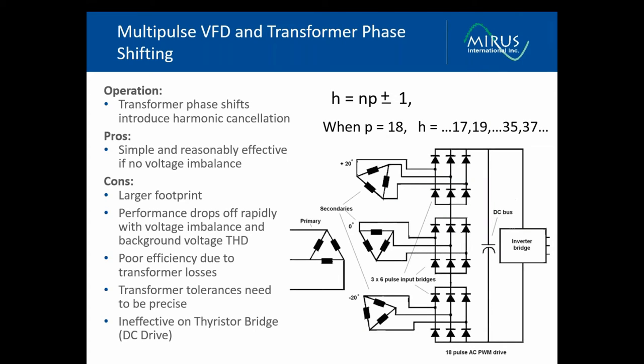Multipulse VFDs, 12, 18, 24 pulse or so, or transformer phase shifting strategies are also very commonly used and can provide reasonably effective reduction of current harmonics in VFD applications. There are conditions, however, with respect to the performance: whether the power system is reasonably balanced, the voltages are reasonably balanced, and whether there's existing background voltage distortion. Voltage imbalance may or may not be a major issue in marine applications, but background voltage distortion certainly is, and that can affect the performance of multipulse drive systems. Also, as mentioned earlier, multipulse phase shifting strategies are not effective at all on thyristor bridges or SCRs, so if you have DC drives, it is not a good strategy to use.